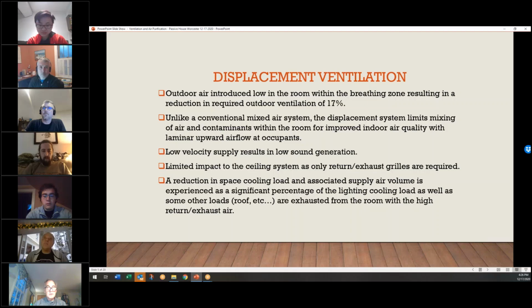So you don't get, unlike a mixed air system that would really blend the air in the room, mix it up a lot. The displacement system is trying to actually make the air in the room divide almost like it would in a cooler, where you have hot air above your head and cool air below. And so there's a few benefits to that besides just the ventilation. Your loads in the room are actually reduced because you're taking a lot of the heat out high. Most of your lighting load is getting drawn out and not getting impacted into the breathing zone of the room, that 6-foot level.